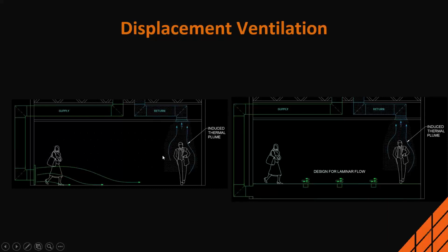So we capture the contaminants that way. This works great if I'm in a cooling dominated area without a lot of heating or perimeter zones. But as soon as I go into heating mode, this distribution method won't work — the air comes out and goes straight to the ceiling, and I won't induce any thermal plumes with the hot air. So it kind of falls apart there.